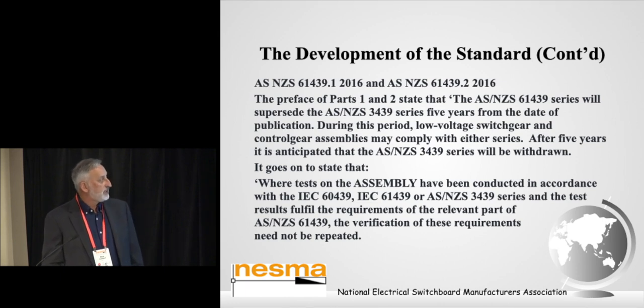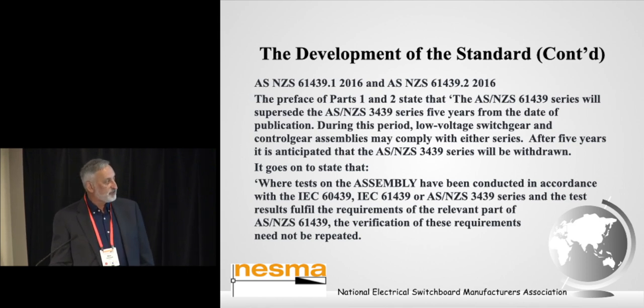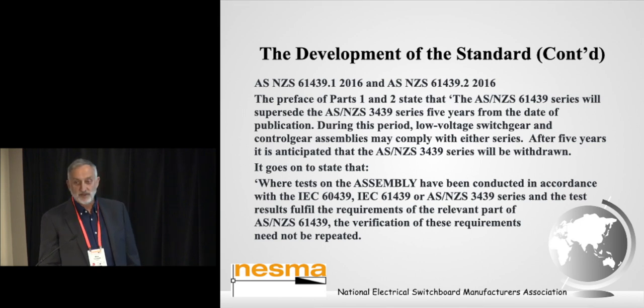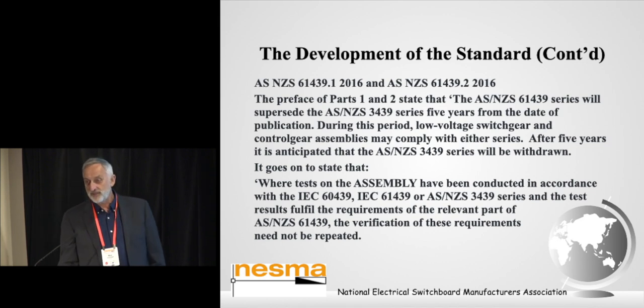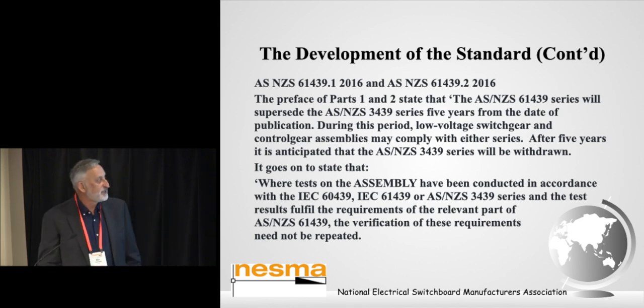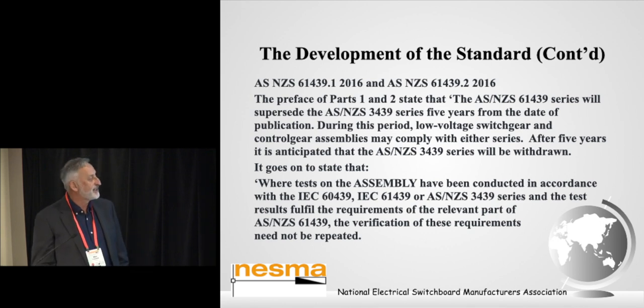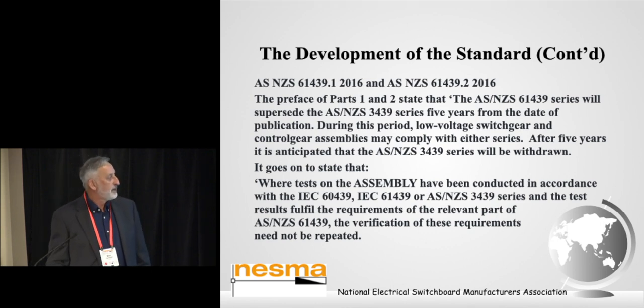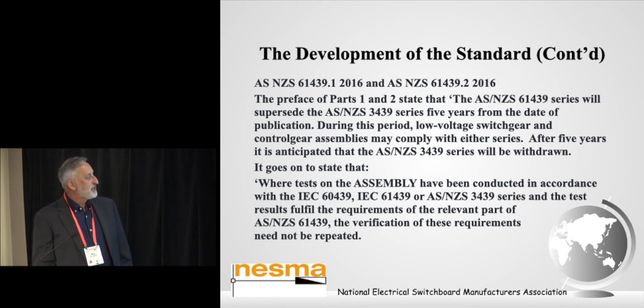So the AS Part 1 and Part 2, in the preface of Part 1 and 2, state that the AS-NZS 61439 series will supersede 3439 5 years from the date of publication, which is 5 years from 2016, which gives us 2021, hence the problem in industry over the last year or so. During this period, low voltage switchgear and control gear assemblies may comply with either series, and after the 5 years it is anticipated that the 3439 series will be withdrawn.